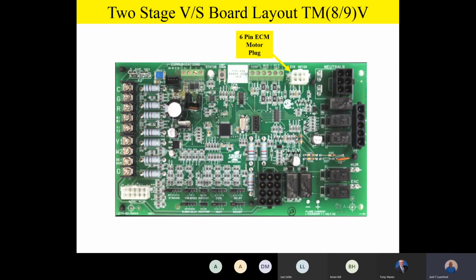This is a 6-pin plug that goes down to the motor to command the motor what to do. Now, those are going to be 24 volt outputs. And so just like before, all ECM motors have power to them all the time, and we're going to tell it what to do with 24 volt commands. And that's what's going to command that motor by that 6-pin ECM motor plug from the board. As we come around the board, we've got some neutral terminals, some spade terminals, as well as a 6-pin neutral plug. And then again, that'll all be harnessed in from the factory. All the neutrals will come to that point.